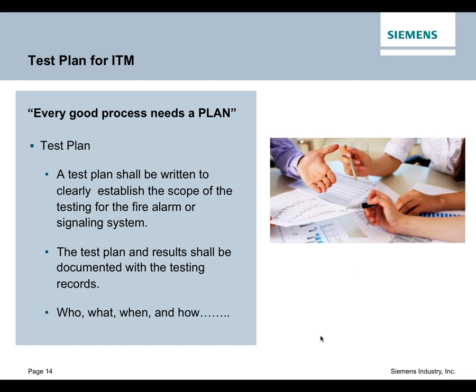And this stuff all revolves around a plan. Every good process, because this mission of providing good fire life safety in your building is a process, and every good process needs a plan. The words that we have here on the screen are actually based on NFPA 72, but they're very similar in 25, and that is that there is a requirement that a test plan be written, a plan that clearly establishes the scope of the testing for the fire alarm and signaling system. A test plan and the results shall be documented, and it needs to have the who, what, when, and how. And what does that really mean?